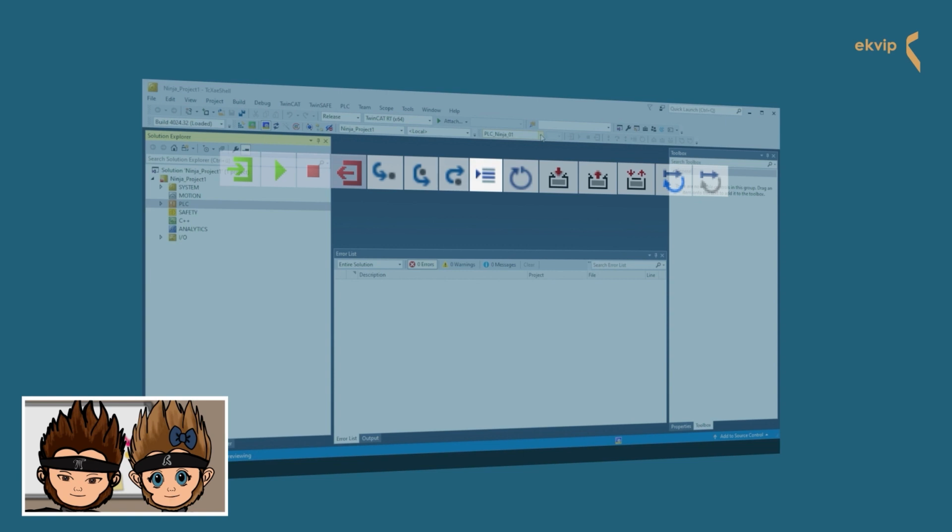If you press the toggle flow control mode, the command activates or deactivates the flow control. The single cycle button. This command executes the active PLC program for one cycle. Pressing the force values button permanently sets the value of a variable on the controller to a predefined value. The unforce value command resets the forcing of all variables. The variables get their current value from the controller. The write values command once sets the value of a variable on the controller to a predefined value.